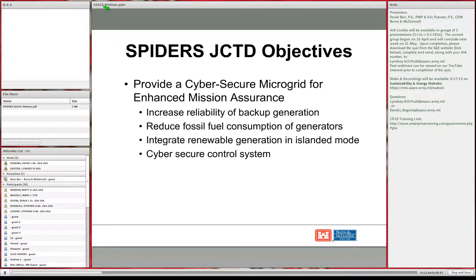The one-line for phase one used a single feeder from the substation through the distribution network, tying in the renewable island—a PV array, a flow battery, and connections for future wind turbines—then to transfer switches serving the two generators and their individual loads. Rather than replacing transfer switches, a bypass breaker was added to allow the transfer switch to operate normally while providing the extra flexibility to parallel power across both the normal and emergency sides. This means any generator can serve its own load or feed the entire distribution network.